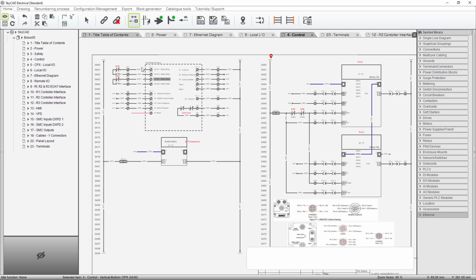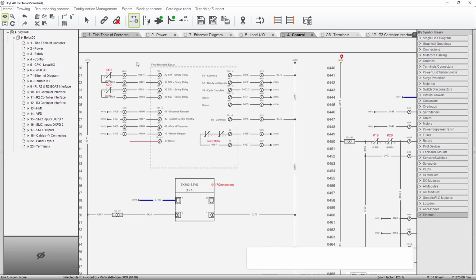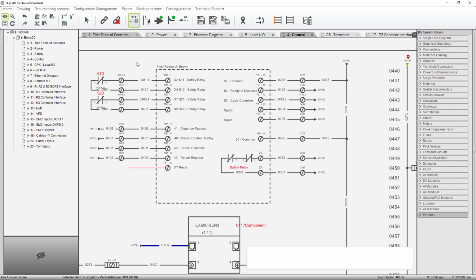Okay, so let's take this first device. So I'm going to zoom in on this. This is the epoxy dispense. Remember that this epoxy dispense is its own complete separate system that will work without our PLC, without our panel. But we don't want it to. We want to control it with external signals. One of the external signals is e-stop. If we hit an e-stop on our panel, the main panel, or anywhere in our work cell, we want the epoxy dispense to go into e-stop as well.